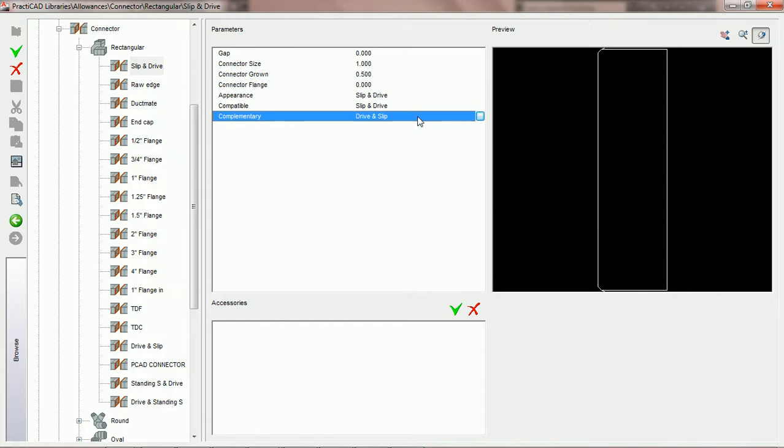In other words, we need to decide with a slip and drive connection what side the drive is going on and what side the slip is going on. And there's a couple different philosophies on what is the right way to do this. There are two main philosophies that you get between contractors. One philosophy says that whenever we decide what side of a fitting gets the drive, it will always be on the long side. Another philosophy says that whenever we decide what side of a fitting should get the drive, we always put the drive on the short side.